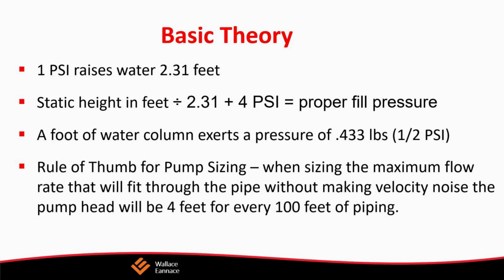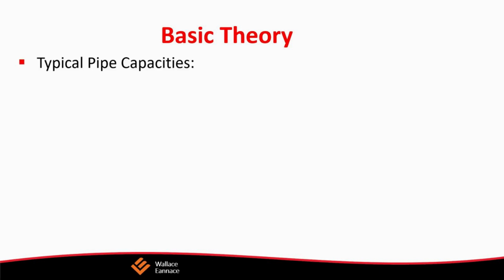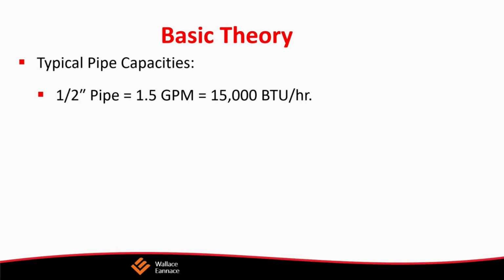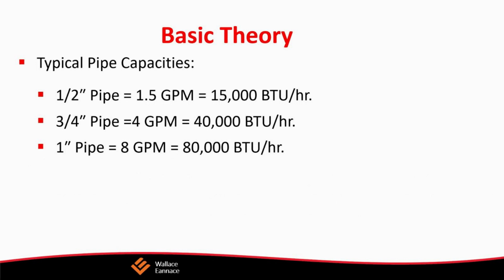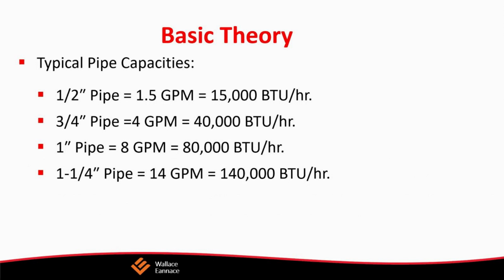So let's talk a little bit about the pressure inside. We've talked about the flow in the pipe, and there's also a relationship we need to talk about, which is the pressure. So let's go back to another definition. If we had a cylinder that was not 1 inch in diameter, but 1 inch square, exactly 1 square inch, and we put 1 pound of pressure on it, and this was a U-tube cylinder, it would move the water up 2.31 feet. So 1 pound of pressure per square inch will raise the water 2.31 feet. So the static height in feet divided by 2.31 plus 4 psi will give us the proper fill pressure.